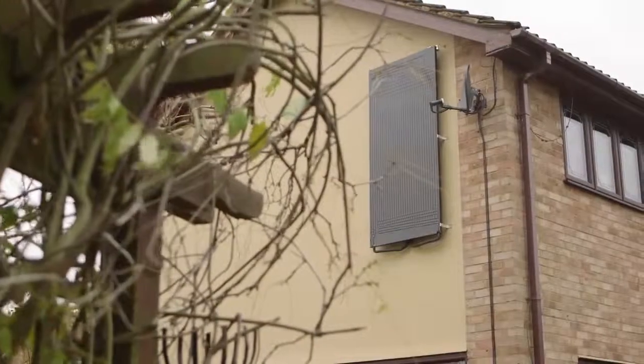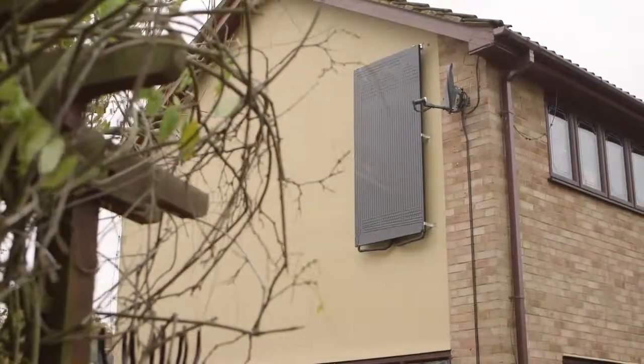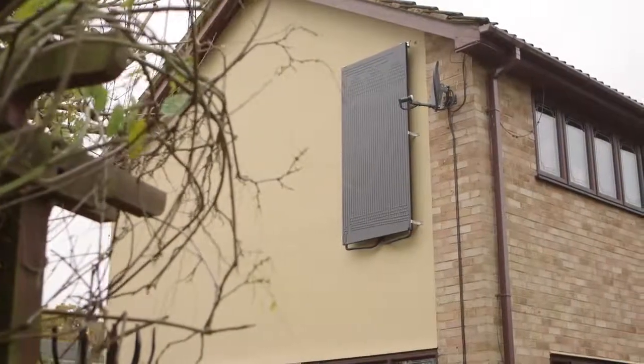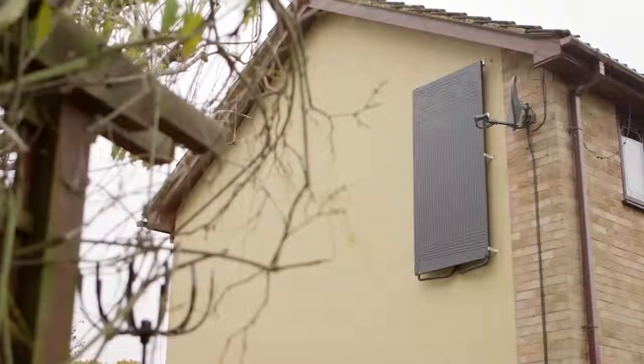We place one thermodynamic panel on an exterior wall of the property, such as here. The panel is made of aluminium and is very durable. It acts as an evaporator and contains a man-made blend of refrigeration gas known as R134A. This gas is ozone friendly. The panel absorbs energy from the ambient air and also from the environments of wind, rain, etc.